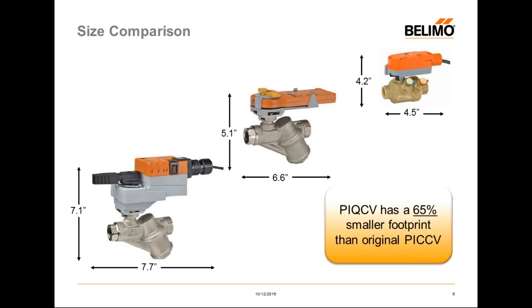This lends itself to additional applications where traditionally you might have had to put a two-way valve and a manual circuit setter. In this case, you can have your control valve and your pressure-independent valve all in one.